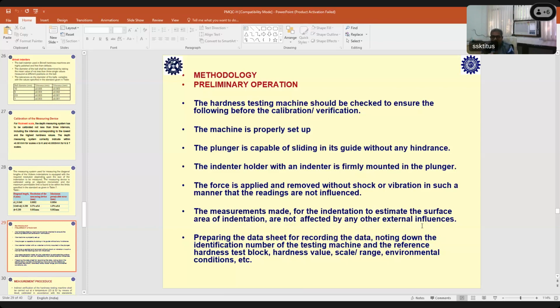So we have to make sure this kind of external thing does not influence the dimensional measurement that you are making on the sample after making the indentation. So you have to clean it carefully, and you have to see that there is no other foreign particle present on the surface which may influence your ultimate diagonal measurement, or the diameter measurement that you are making on the sample after the indentation.